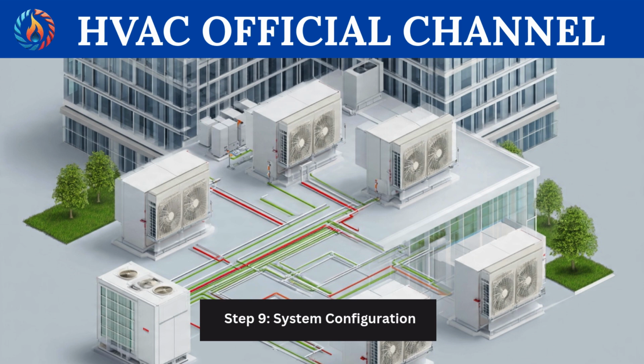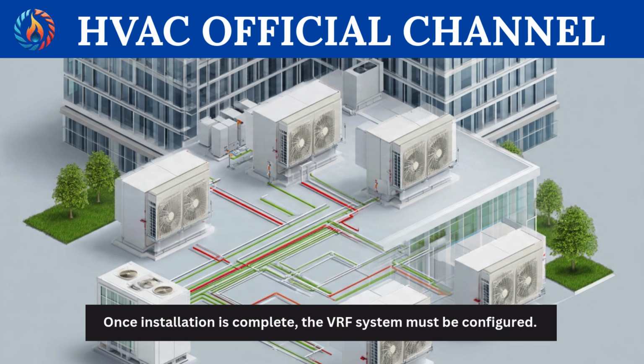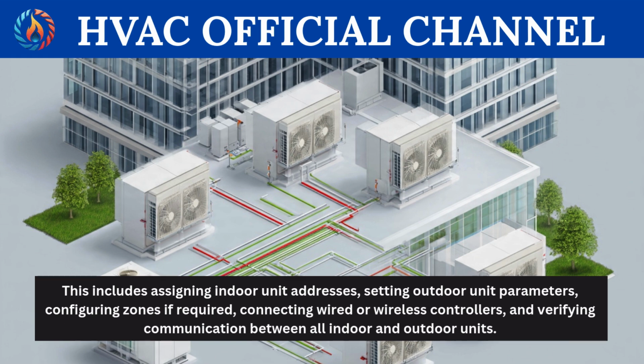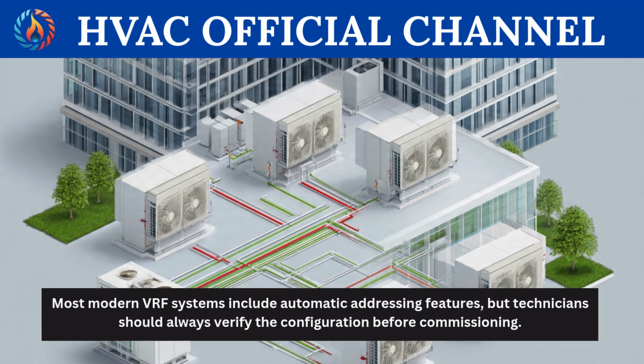Step 9. System configuration. Once installation is complete, the VRF system must be configured. This includes assigning indoor unit addresses, setting outdoor unit parameters, configuring zones if required, connecting wired or wireless controllers, and verifying communication between all indoor and outdoor units. Most modern VRF systems include automatic addressing features, but technicians should always verify the configuration before commissioning.